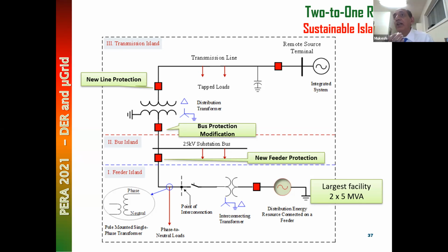So, if you have a cable, protection desensitization is not a big issue because the fault resistance is low. As long as you have IBRs, cables are not a problem. But if your microgrid is formed by a conventional synchronous generator, which has an inductive source, you have to look for another issue. Will it form a near 60 Hz resonance? Actually, that is covered in quite some detail in my paper.